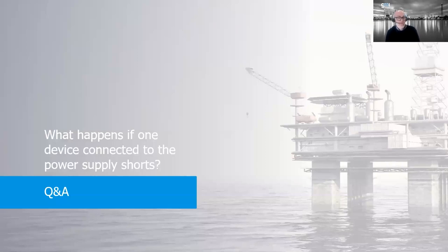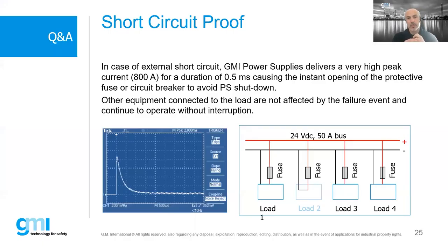Perfect. And to finish our presentation, what happens if one device connected, one load connected to the power supply is in short condition? Well, basically all power supplies, when there is a short, stop working, so they go to zero. We developed special features on our power supplies so that in case a fault is detected, a very high peak of current, we talk about 800 amps for 0.5 milliseconds, so a very short time, is delivered. This current causes the instant opening of the protective fuse or circuit breaker, avoiding the shutdown. This is a special feature that we implement into the power supply for protecting our system.